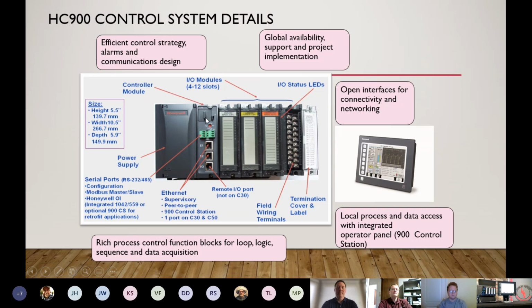The next is your CPU or controller module. There's actually 4 different variations of the CPU module. We have a C30, a C50, a C70, and a C75R for redundancy. At the very top, there is a slot for a battery. That battery has a backup battery in it as well. This is something that holds some of the non-volatile memory with the real-time clock and things like that.